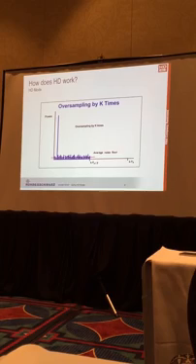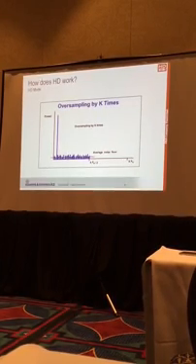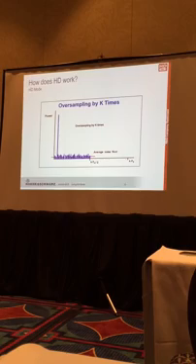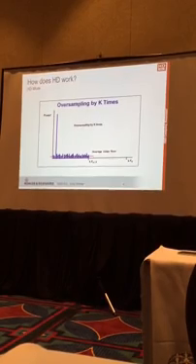So in our HD mode, we do just that. Our A to D converter runs at 10 gigasamples per second in the RTO, 5 gigasamples per second in the RTE. If we reduce the bandwidth using a digital filter and then lower the sample rate, we basically take the existing quantization noise, which is spread over the whole 1 gigahertz bandwidth or whatever scope you have, to that 3, 5 megahertz range or whatever you set it to. And so you essentially gain more bits. Approximately it's 1 bit for every quartering of the sample rate. And that's where we get the 16 bits from.